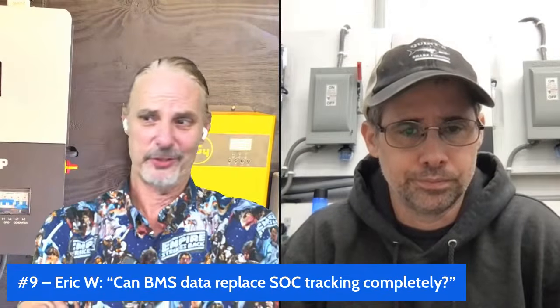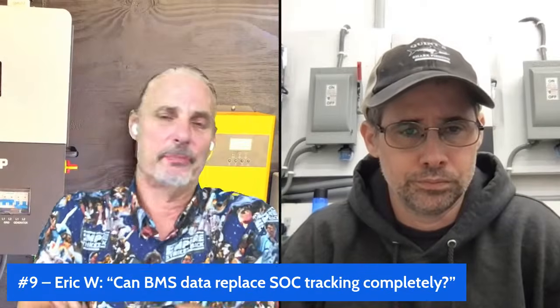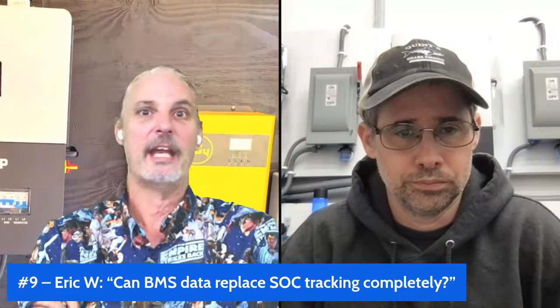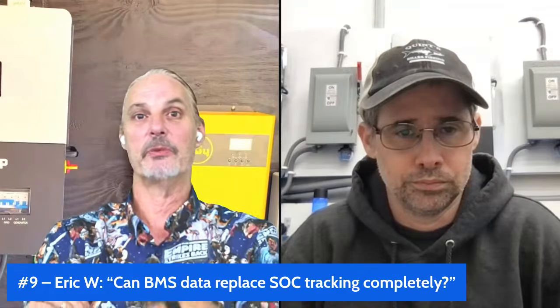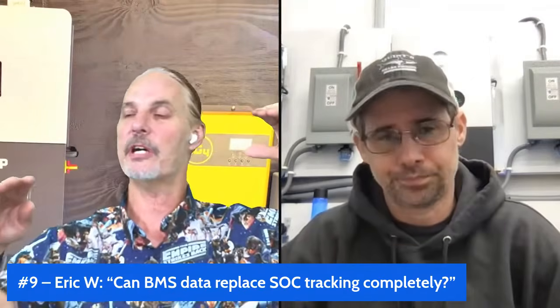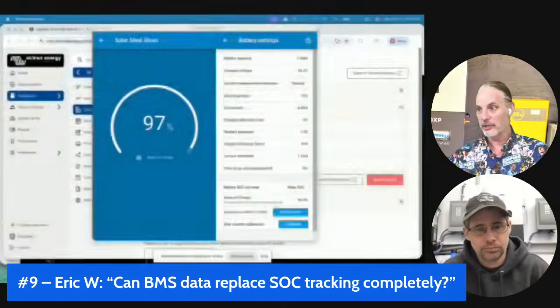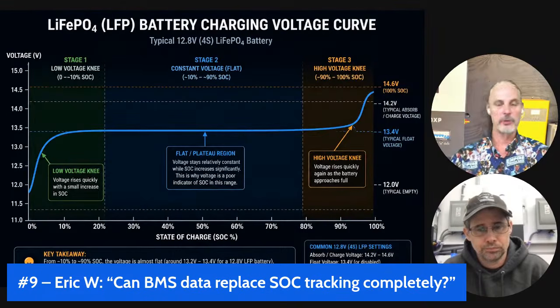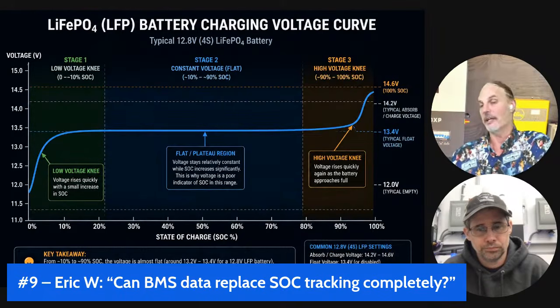And the answer is, if you're talking about voltage, then sure. State of charge is a recent addition to solar. For years and years, lead acid batteries used voltage, and it was never a big deal because there was a curve that slowly decayed over time, so you could easily say that at this voltage you had this amount of charge. The only reason that's changed is because now you have this bell curve where for a long period of time, 80% of the time, voltage is almost exactly the same, and it's almost impossible to determine from day to day where your batteries are. That's the only reason there's a difference.